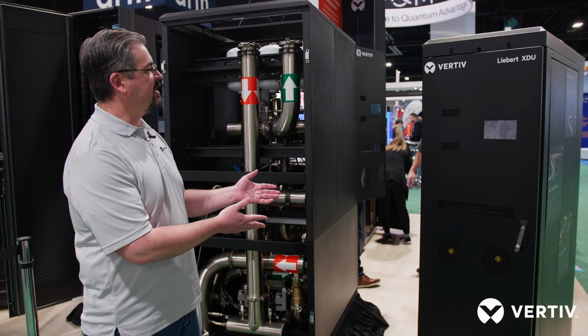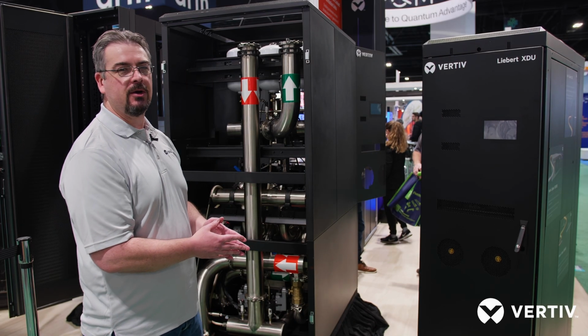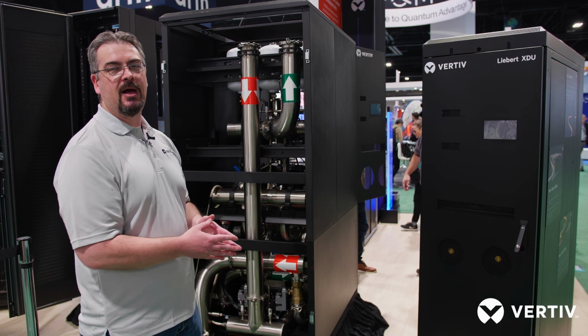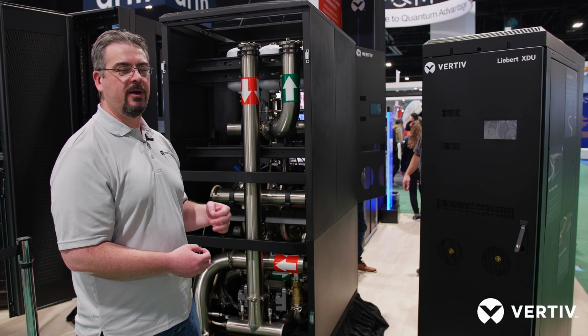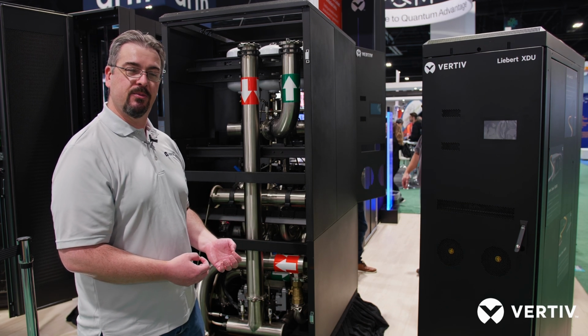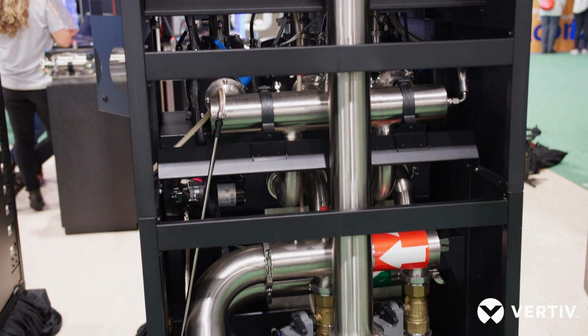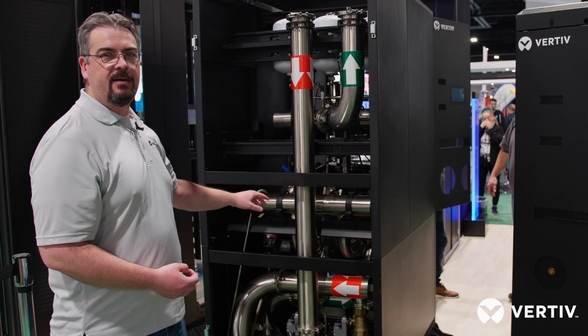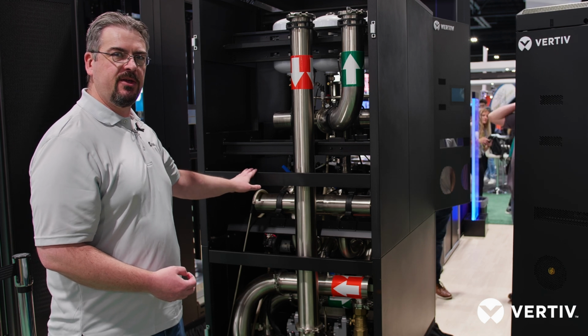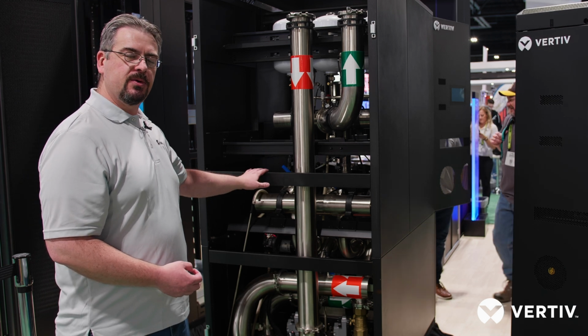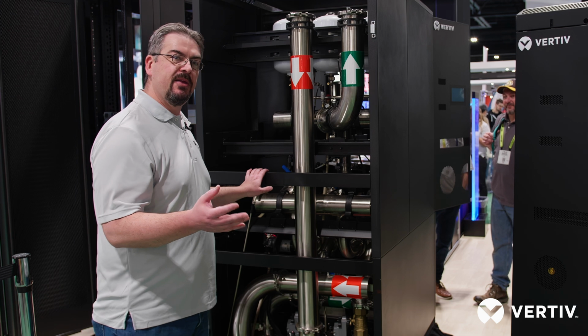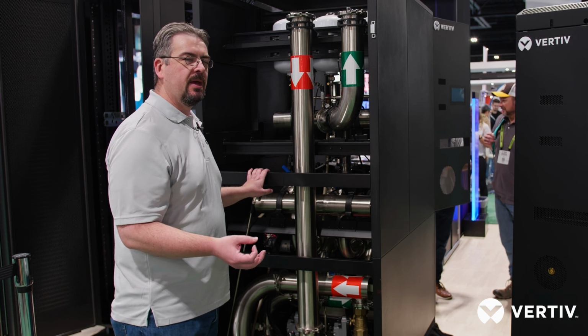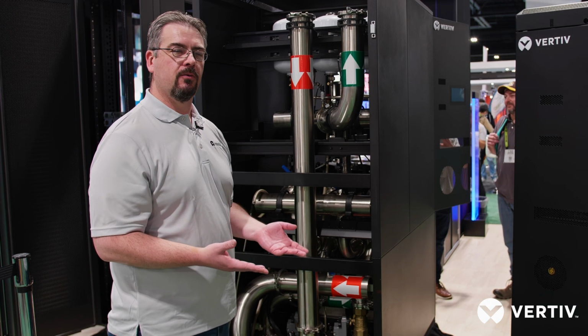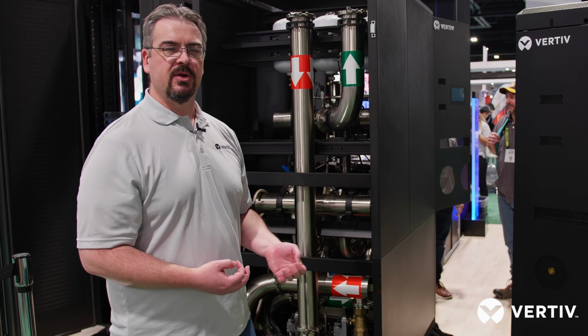So filtration is the number one concern when talking about cold plates, and this product allows these cold plate deployers to operate with security, knowing that their equipment has been protected. The CDU operates by taking that chilled water, running it through what we call the primary loop, and exchanging that heat in a liquid-to-liquid heat exchanger inside the unit. We then use pumps within the unit to circulate fluid on the secondary side to the racks and provide, again, that temperature, flow rate, and pressure that the servers need to operate efficiently.